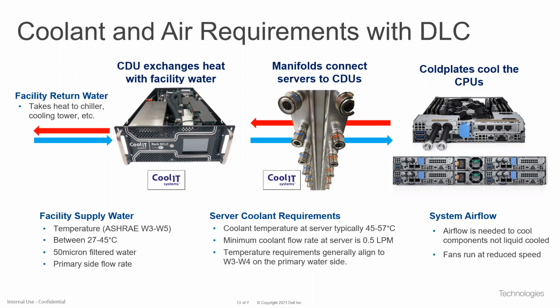But functionally, they do the same thing, in that as the coolant comes back from the IT with elevated temperature, it goes to the CDU and it exchanges that heat energy to the cold plate that's inside the CDU connected to the facility water. What then goes back to the IT is the cool temperature coolant that is primed to absorb all of the heat off of the CPUs.